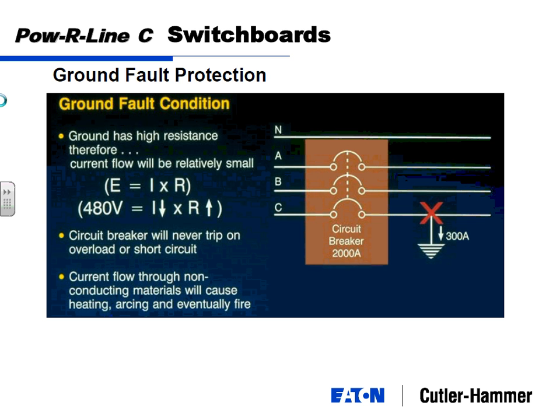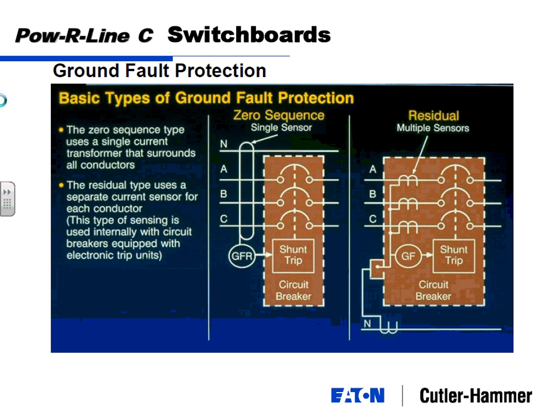Oh, okay, so but it's not the same as a human protective ground fault at 6 milliamps or below. Correct. Much different. In fact, I think this is too low. Typically, a 2,000 amp, you'd probably set it up as 500 or 1,000 amps ground fault protection. Yeah, there's 5 milliamp and 30 milliamp ground fault protectors that, for example, you'd have at your home, in your spa, or in your bathroom. This is a full fault. Yeah, same concept, but bigger. So that's why you have to have special ground fault protection, because your currents are going to be much less.